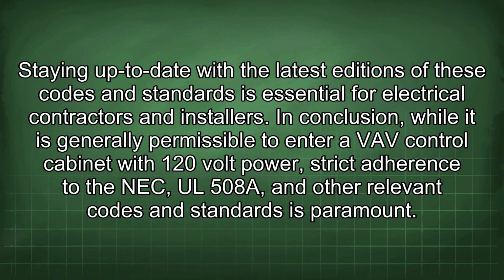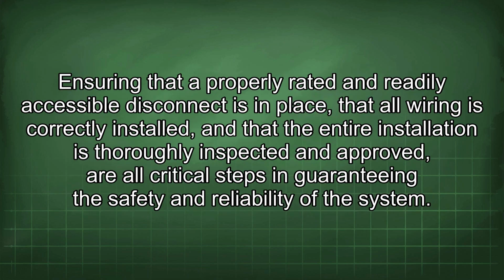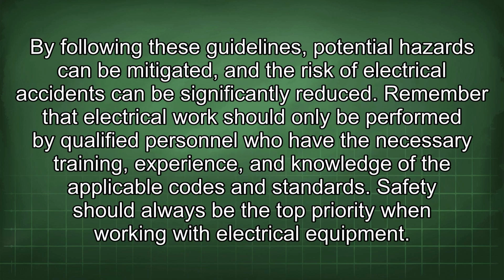In conclusion, while it is generally permissible to enter a VAV control cabinet with 120 volt power, strict adherence to the NEC, UL 508A, and other relevant codes and standards is paramount. Ensuring that a properly rated and readily accessible disconnect is in place, that all wiring is correctly installed, and that the entire installation is thoroughly inspected and approved, are all critical steps in guaranteeing the safety and reliability of the system. By following these guidelines, potential hazards can be mitigated, and the risk of electrical accidents can be significantly reduced.